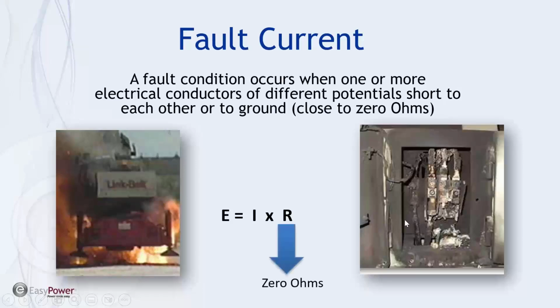The same thing happens. So in a fault situation, what I'm doing is taking one phase and going to ground, or I'm going from one phase to another phase. And what I normally have in my electrical infrastructure is very high resistance between one phase and another, or one phase and ground. And we have to maintain that high resistance. That's part of doing maintenance, making sure the insulation is good between those parts and ground, or from phase to phase. So when that gets breached, say a screwdriver gets placed across two phases, and they're live phases, now what we're doing is dropping resistance from a very high resistance, the way it's normally set up, to a very low resistance, and we're going to call it 0 ohms.